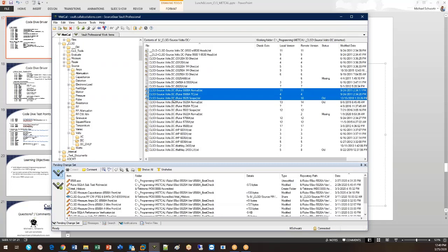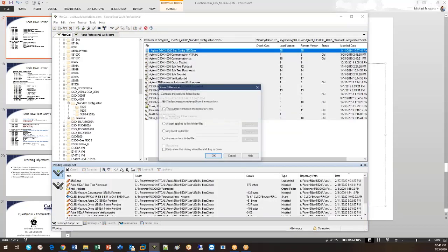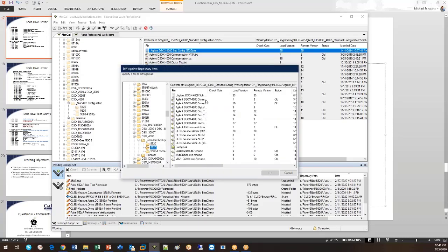So when I left MetCal, I changed my model to where each driver supports one standard and it supports one output on that standard. And then I do all of the interchangeability at that subconfig level. So when we jump down to this 5520, I'm going to look at this one, I think I can diff this versus another one. Yeah, this will let me do that.